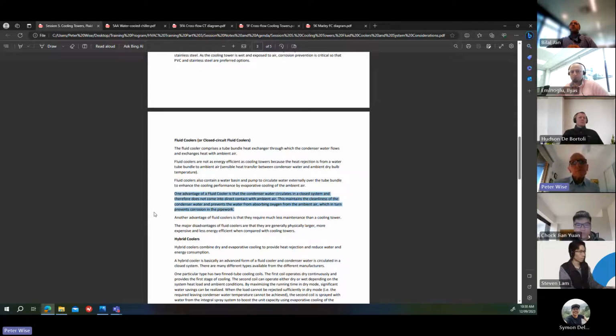for instance, if you've got a water-cooled packaged air conditioning system, you've got a lot of, as I said before, you might have 100 of these packaged units around the place. It's really critical. They've got very small condensers, and if they get blocked up with dirt, they're very hard to clean. So in that case, you might consider a fluid cooler because that'll keep the water clean. With a water-cooled chiller, they're larger tubes, they're relatively easy to clean, and a cooling tower is more efficient. So horses for courses, you can choose which is more appropriate for the project.